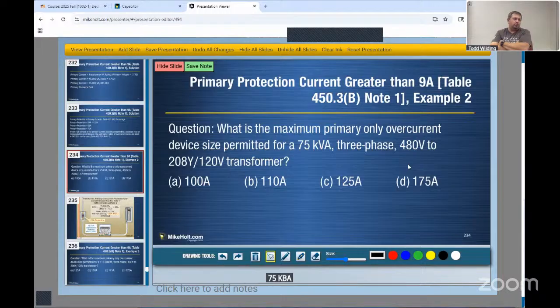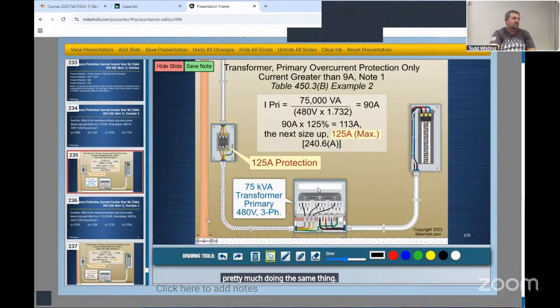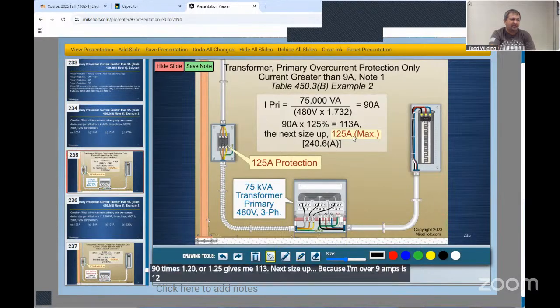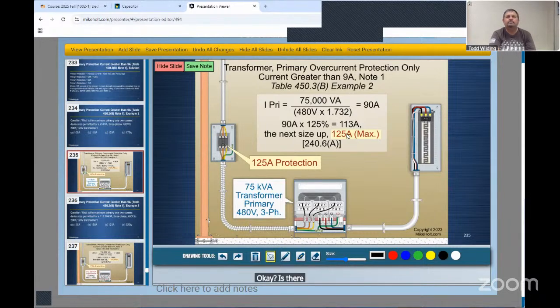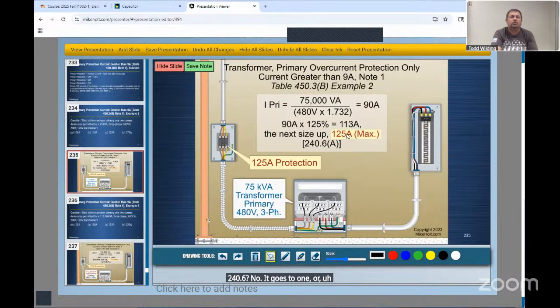Okay. Next one, a little bit bigger. 75 kVA, 3-phase 480 into 208/120: 100 amp, 110, 125, or 175? Pretty much doing the same thing. 75,000 divided by the 480 times 1.732 gives me 90 amps. 90 times 1.25 gives me 113. The next size up, because I'm over, is 125. That would be max. That's as max as I can go. Is there a 120 amp breaker? 240.6? No. It goes 110 to 125, according to 240.6. Yeah, 110, 125. I knew there was something in there.